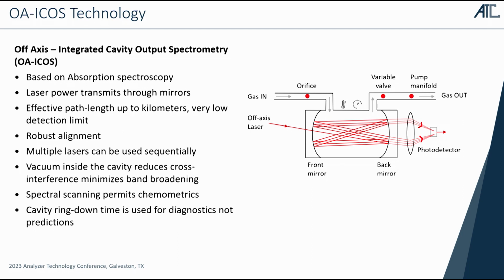And something to remember, these are near-infrared lasers. Whenever you're talking near-infrared spectroscopy, I don't care if it's a spectrometer or a laser-based technology, with chemometrics, fundamentally, and I know I'm going to get a lecture after I say this, but fundamentally, you're taking a nonlinear response and forcing it to a linear curve. And what PLS brings to the table is maybe an expanded range over a standard y equals mx plus b. But the other thing it brings to the table is you can trend beyond the range of the analyzer calibration. It may not be very accurate, but it's good enough to see increases and decreases reliably for process control.